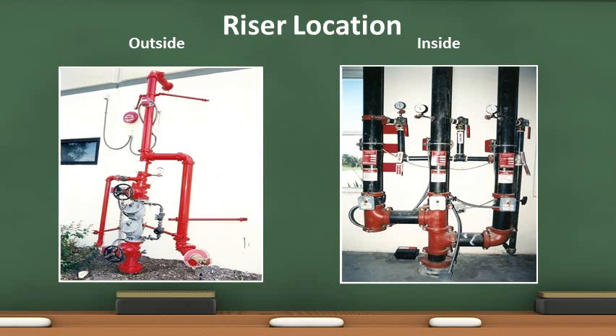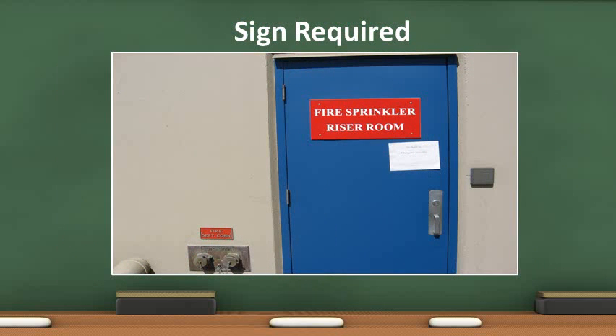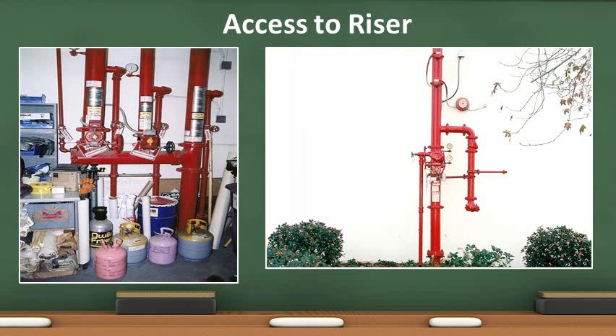These photos show examples of two types of sprinkler risers. Risers may be located outside or inside the building. If fire sprinkler risers are located inside a room, a sign on the door to the riser room is required. Keys for the door shall be located inside a key box. Access to all fire protection equipment is required. Nothing of any kind shall be stored within three feet of all sprinkler equipment, including the riser.